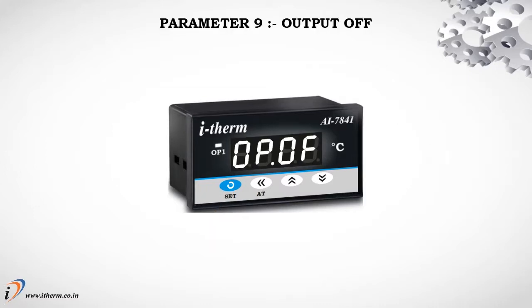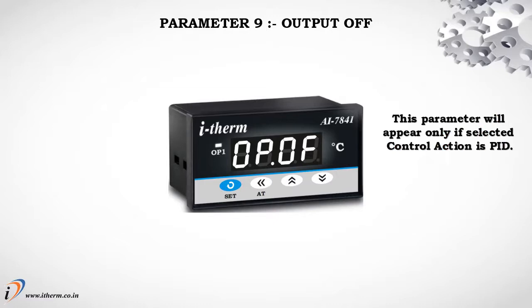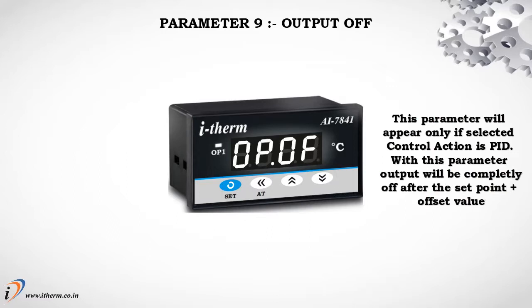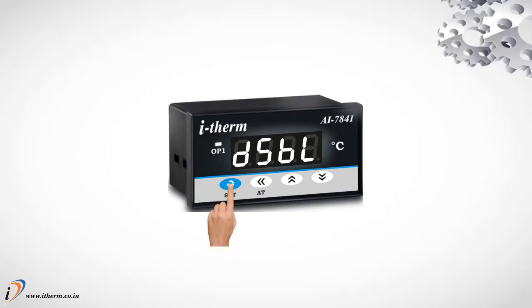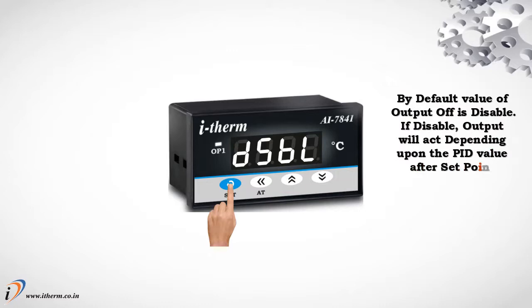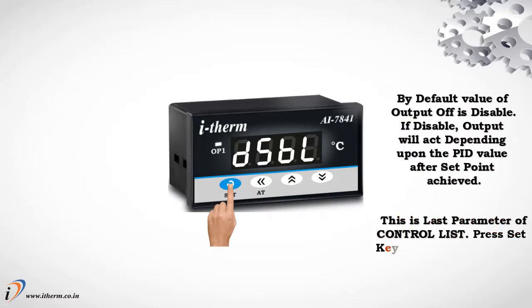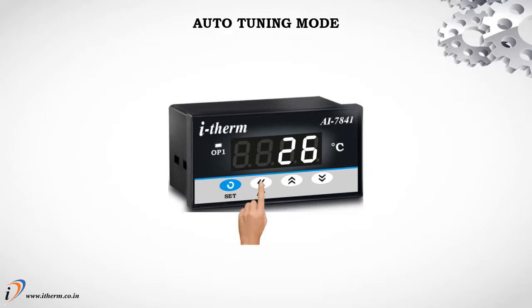Parameter 9, output off. This parameter will appear only if selected control action is PID. With this parameter, output will be completely off after the set point plus offset value. By default, value of output off is disable. If disabled, output will act depending upon the PID value after set point achieved. Default set point offset value is 0. This is last parameter of control mode. Press Set key to enter in auto-tuning mode.